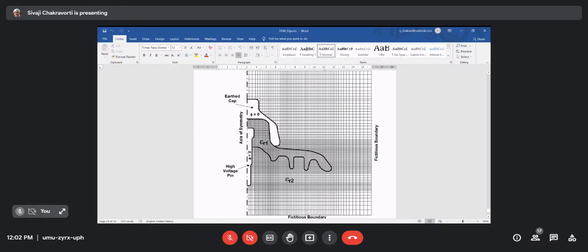Then I have the high voltage pin here, which is at whatever potential, 11 kV, 33 kV, whatever it is. Then this one is the porcelain, which is epsilon R1. This one is epsilon R2, that is air. How to do this for multiple dielectrics I will explain again later. That is now defined; this is my region of interest. Then I discretize. Once I discretize, you take any node here, and you get four nodes which are connected. This is how we go forward.